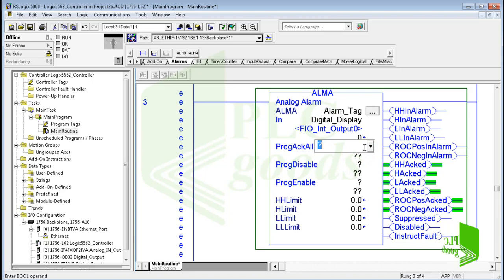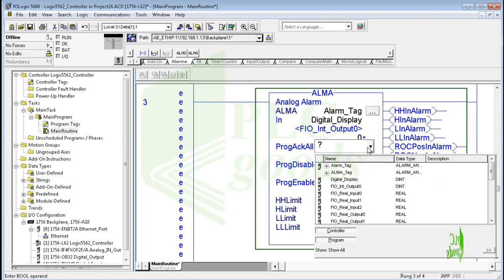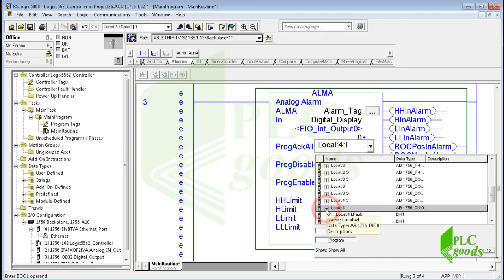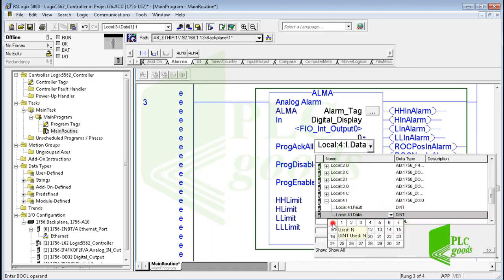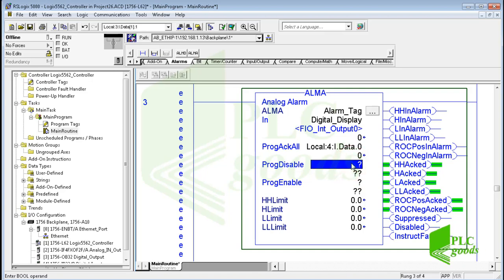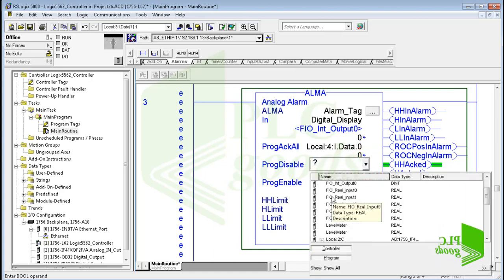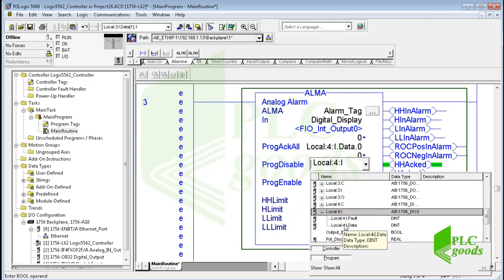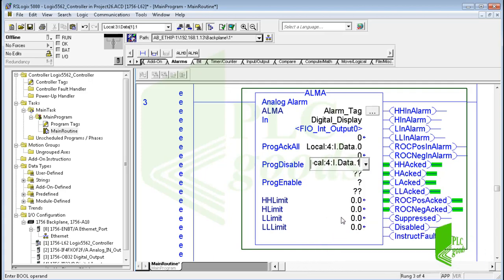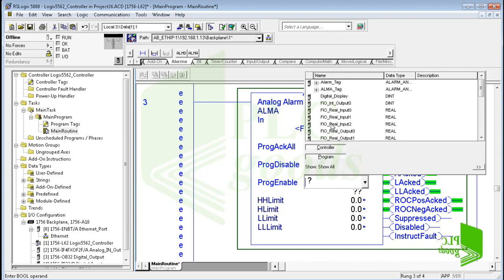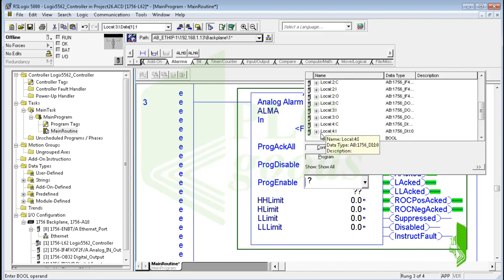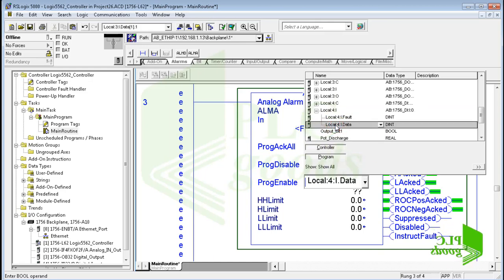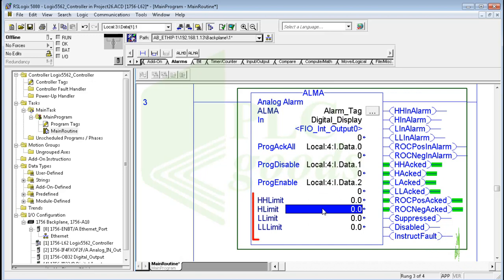The next parameter is program acknowledge, which is set by the user program to acknowledge all conditions of the inserted alarm. It requires a cleared to set transition while the alarm conditions are unacknowledged. Here let me use the first real digital input. Two next parameters, program disable and program enable, are set by the user program to disable or enable the inserted alarm. Similarly, let me use two real digital inputs for them.